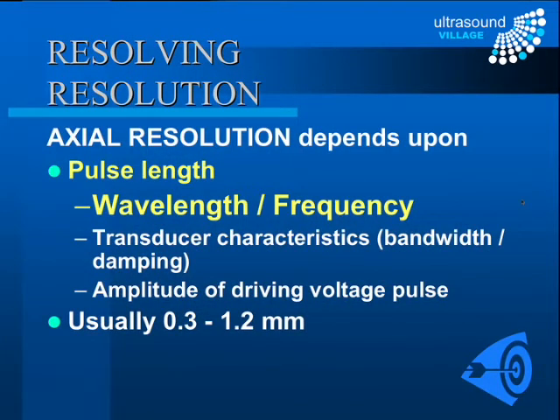We need to talk about resolution — how accurately our machine can locate precise objects and surfaces, particularly small structures. Axial resolution is resolution along the line of the beam, and its primary determinant is the pulse length, which is determined mainly by the wavelength or frequency — they are inversely related. Other characteristics like transducer bandwidth, damping, and driving voltage also matter, but in general with typical machines our axial resolution is between 0.3 and 1.2 millimetres.